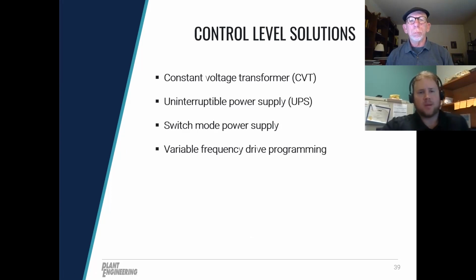So next, we talk about control level solutions. These types of items would be explored if you're having momentary interruptions consistently, like voltage sags. If you have PLCs, programmable logic controllers, or just other basic controllers that are tripping on voltage sags, then you can install something like a constant voltage transformer or add a UPS, uninterruptible power supply, in the circuits. If you have a lot of these PLCs and controls across your facility, you can even add a large centralized UPS that serves all the machines. Or maybe you want to just add a smaller UPS or smaller CVT on each machine individually.